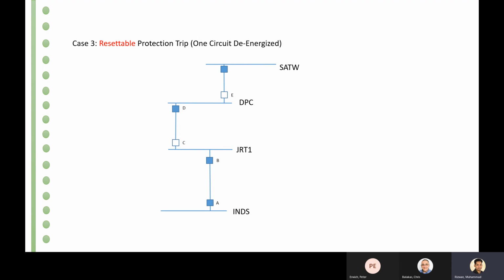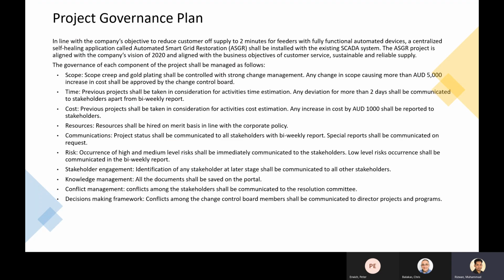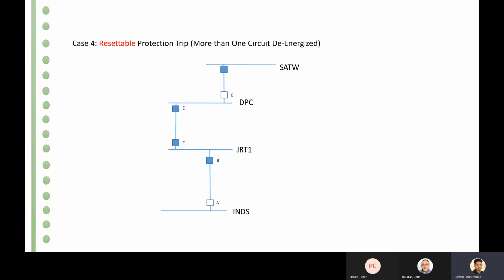In case 4, if the circuit trips from C and circuit breaker CBA opens, it means there will be interruption of 2 substations, which are JRT1 and DPC. So in this case, there will be no restoration of the supply because there are more than one circuit de-energized, between INDS and JRT1 and between JRT1 and DPC. So it is very difficult to find out where the fault is, and the operator will first manually check the location of the fault. He will check the distance of the fault, and then he will take the decision. So ASGR in this case will not take any decision.